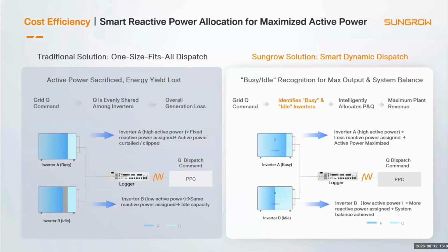Traditional plant control may distribute reactive power evenly across all inverters, but some inverters may already be producing high active power while others still have spare capacity. If reactive power is shared equally, the heavily loaded inverter may need to reduce active power. Sungrow dynamically identifies busy or sleeping inverters, assigning more reactive power to those with available capacity. The grid requirement is still met, but active power generation is maximized.